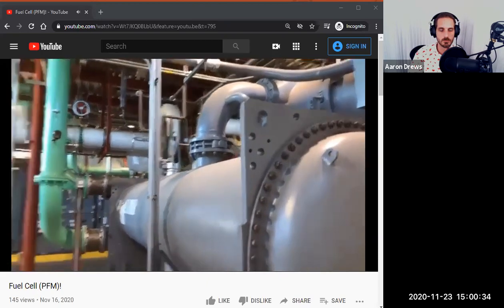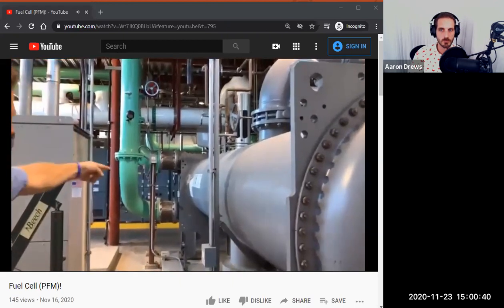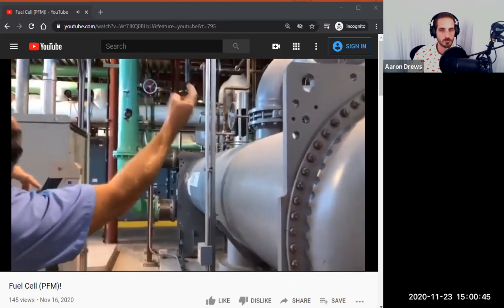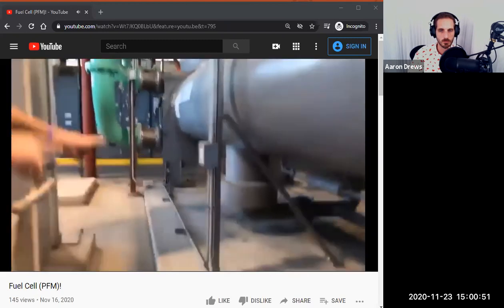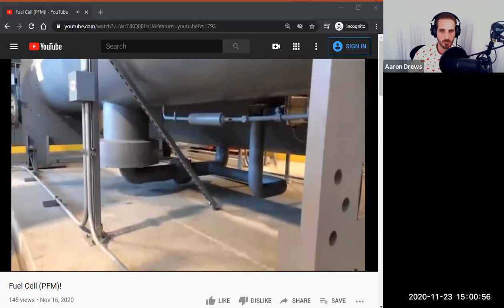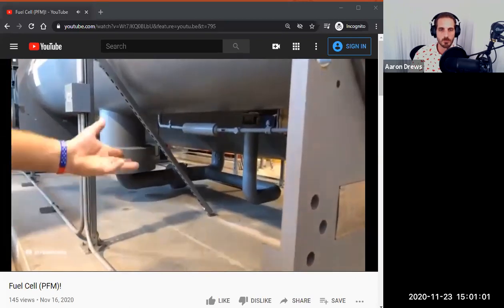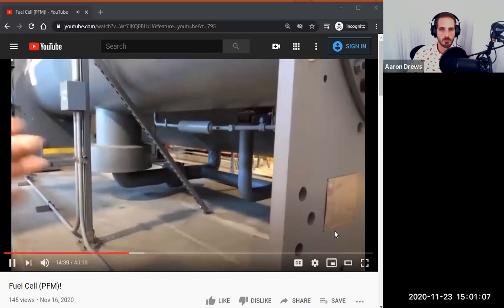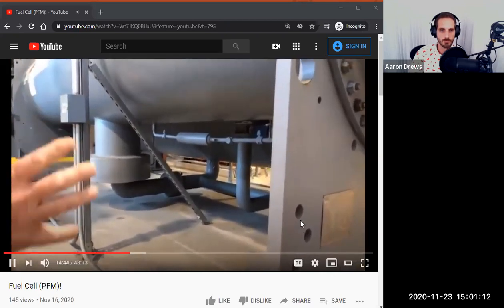Well, the green is the condensing water flowing from the cooling towers, 73 degrees in and back out, and it condenses that vaporized refrigerant back into a liquid. And then down underneath, the liquid then flows back over through a set of control valves, maintaining levels in both.